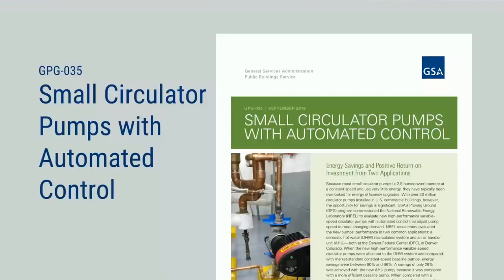All right, so today you're going to hear about small circulator pumps with automated controls. So this is an evaluation that took place, as I mentioned, at the Denver Federal Center. And there were two applications of this. One is in a domestic hot water application, and the other one is in an air handler unit. To understand the application, think about at home when you go take a shower, you turn on the water, the first thing that comes out of your shower head is cold water. And that's because the water in the pipe that goes from your shower head all the way back to your hot water heater has to clear before you get to that hot water. If you think about what happens in a big commercial or federal building, that could be a long run from where that heat source is all the way to where the discharge is. So what typically happens is they put in a circulator line, which has hot water circulating, and that circulation takes place with a pump that moves that water through the line.